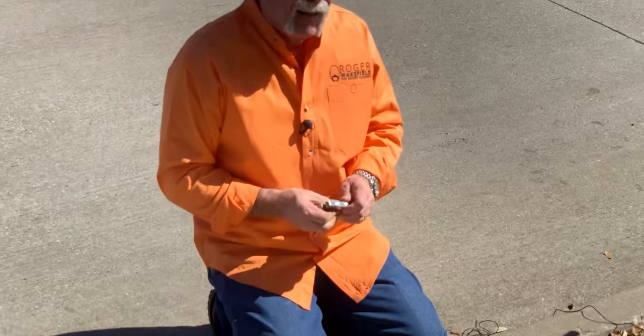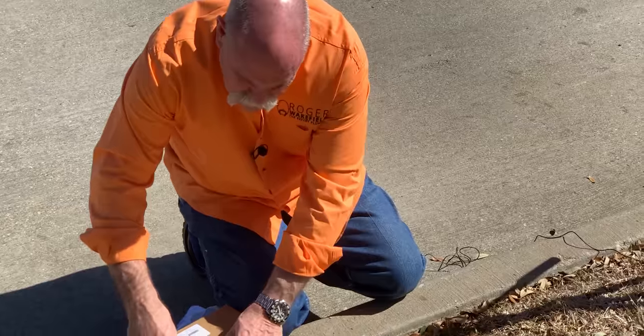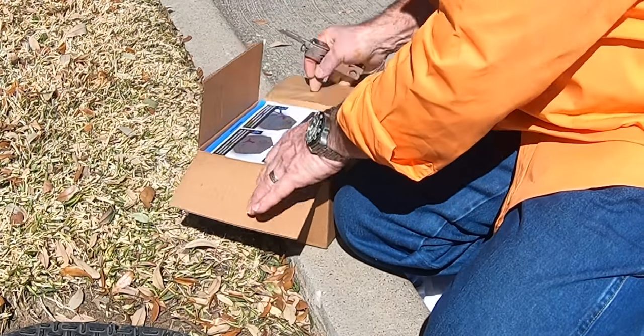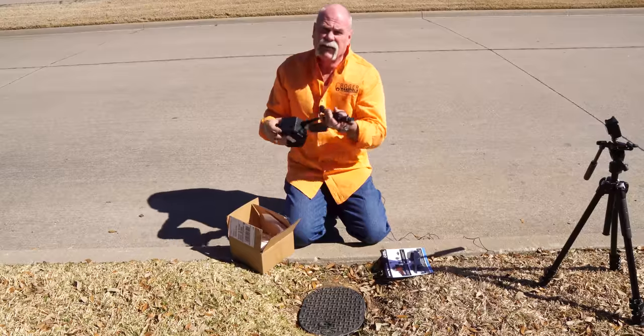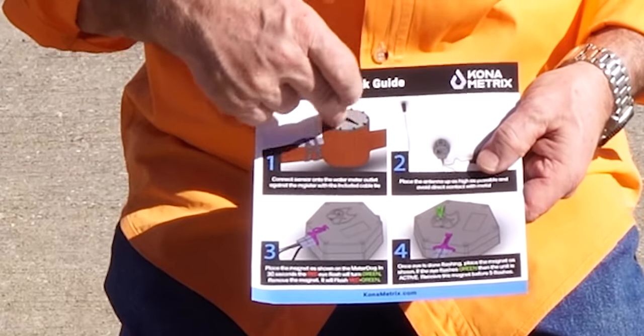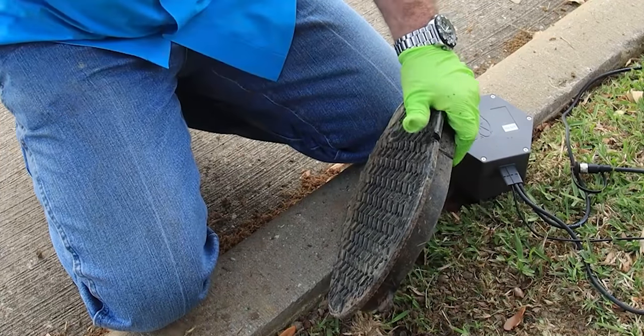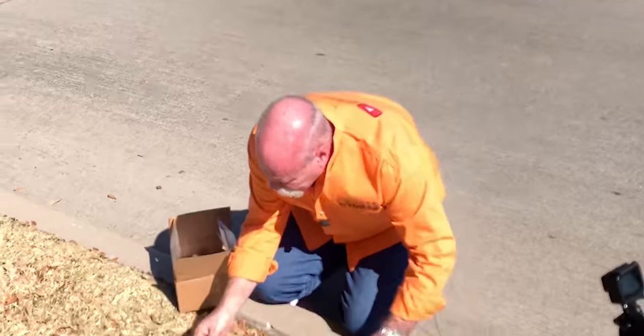So here we are out in the field. I love this thing. What I'm going to do is go ahead and open up the box and show you what all we get with it, and then show you how to do the install. What I've got here is the Meter Dog. I have my quick guide for the install so I know what I need to do, I've got my Meter Dog unit, and I have my magnet to turn it on and off. What I need to do first is connect the sensor on the outlet side of the meter up close to the register, then put my antenna where it goes, and then basically turn it on.